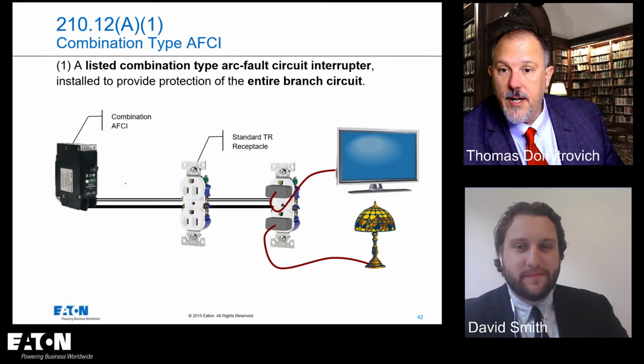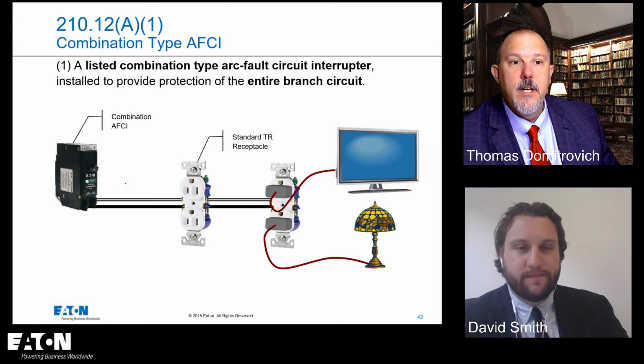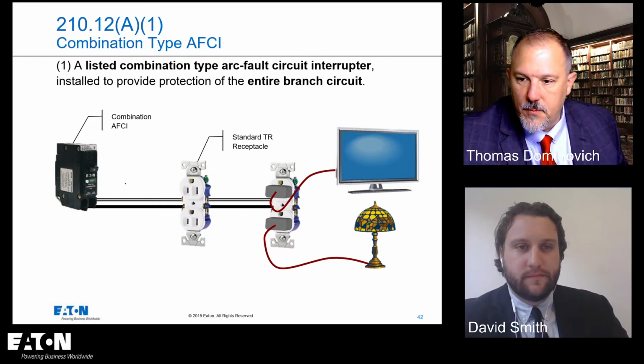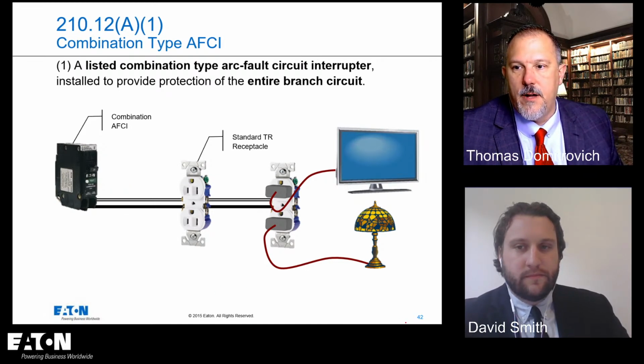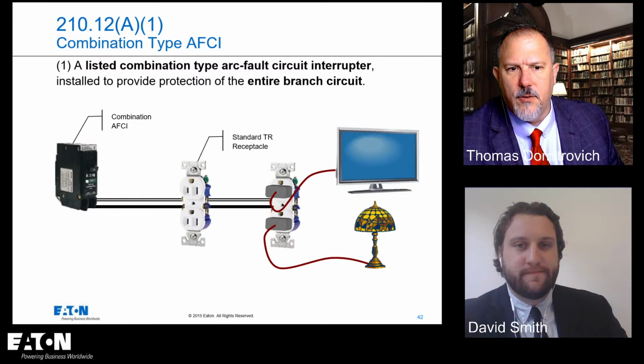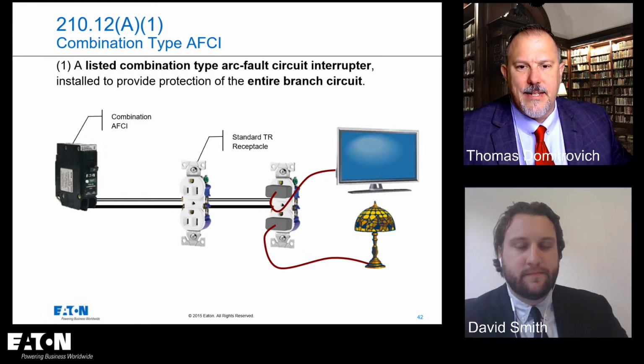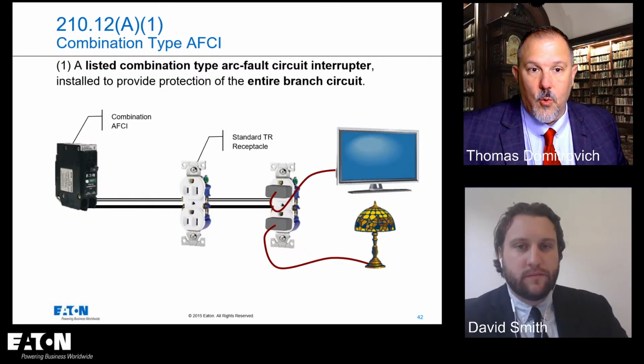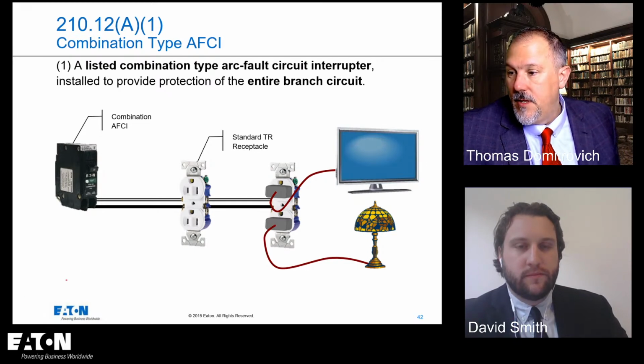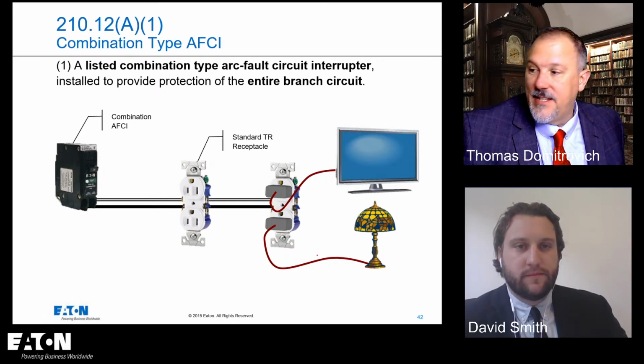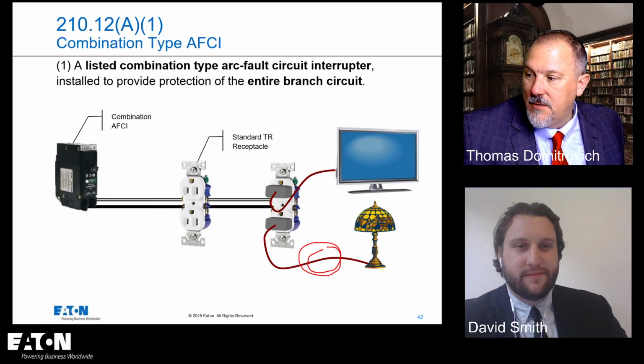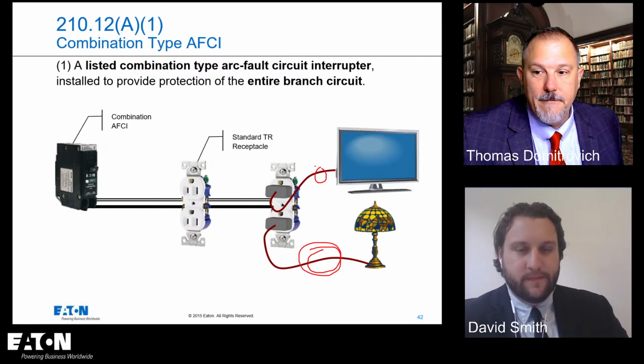So this is your first option, where you have a listed combination type AFCI installed to provide the protection of the entire branch circuit. And from a Panel 2 perspective, this is the passion around the code panel. They want to make sure we protect the entire branch circuit and the connected cords. And what the combination type does is get us that 5 amp series arc for these connected cords, right? Right.